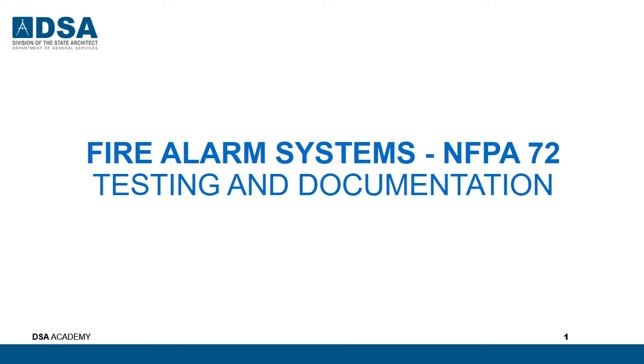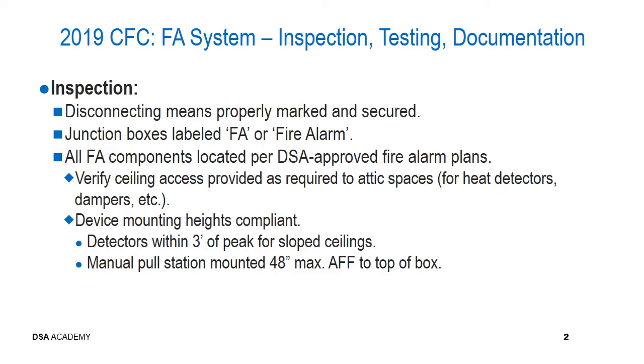Fire alarm systems, testing and documentation. Inspection process. Make sure that the disconnecting means is properly marked and secured. Junction boxes are labeled FA or fire alarm. That the fire alarm components located per the DSA approved plans are correct. Verify the ceiling access is provided as required to any attic spaces or other concealed spaces for heat detectors, dampers, etc.